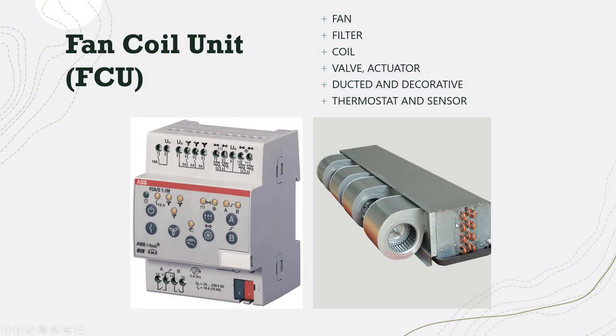The duct includes both supply air and return air ducts. This type of FCU can be controlled in KNX in two ways: using a KNX FCU actuator with connections for fan speed one, two, and three, and controlling the cooling valve as a modulated type. In some applications like hospitality, they use zero-to-ten volt control, where you use a different actuator with a zero-to-ten volt output for the cooling valve. A KNX thermostat is also required.